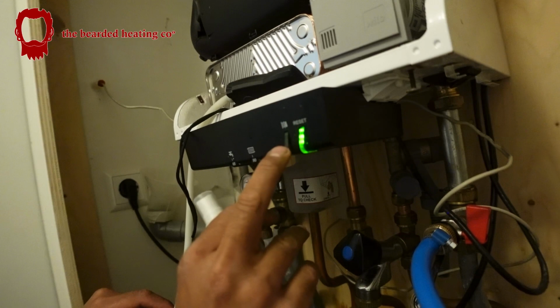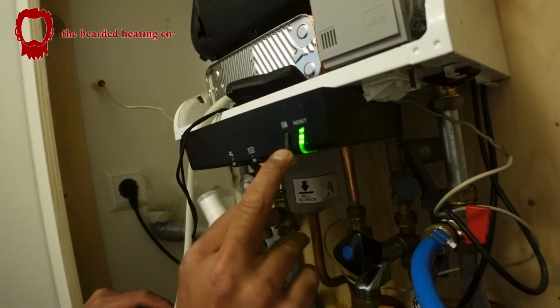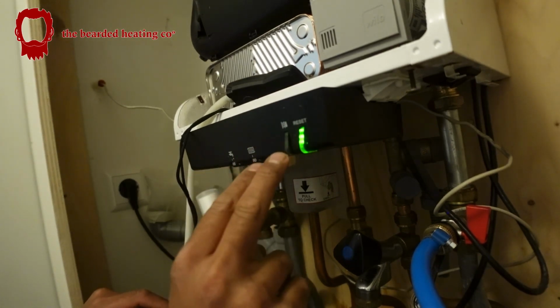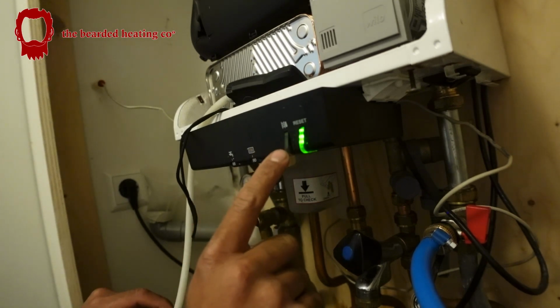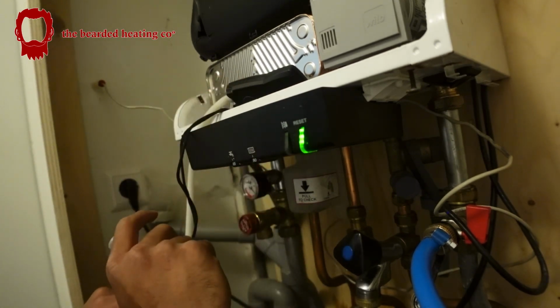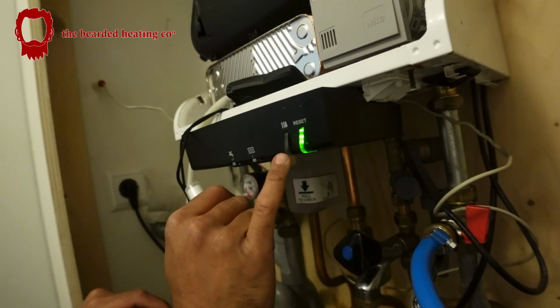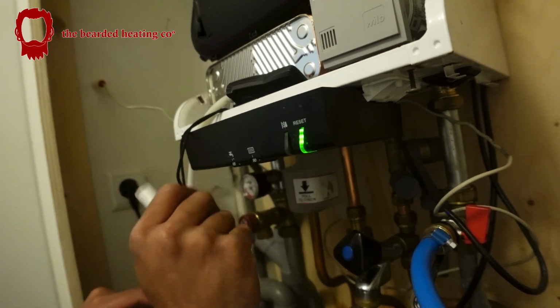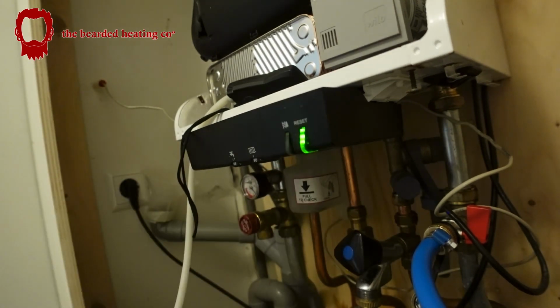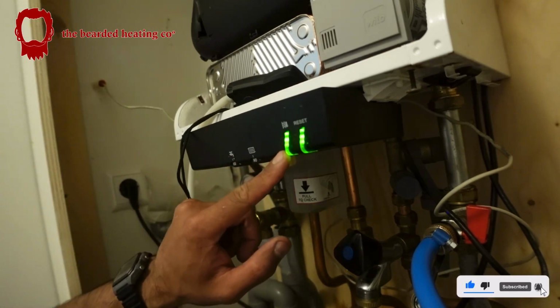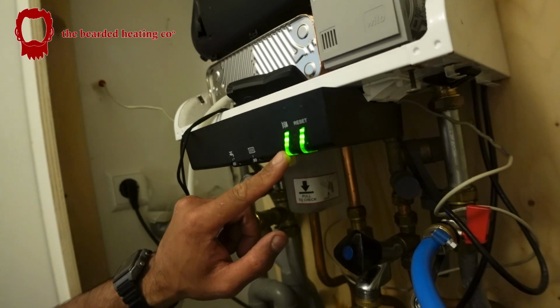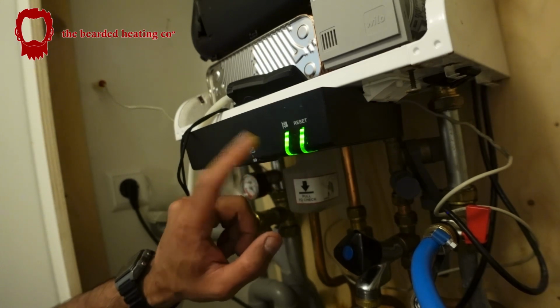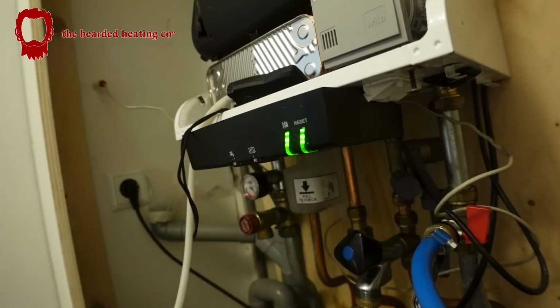When this light is on and it's green, and it turns off twice, that means it's in hot water mode. It's just heated up the plate heat exchanger. And then when it's steady and it flashes only once off, that's heating mode. So now I'm putting the hot water on, and there we have it. So you see, green, steady, and off twice. That's just basically telling you it's in hot water mode.